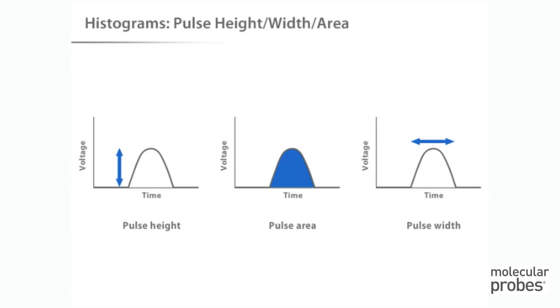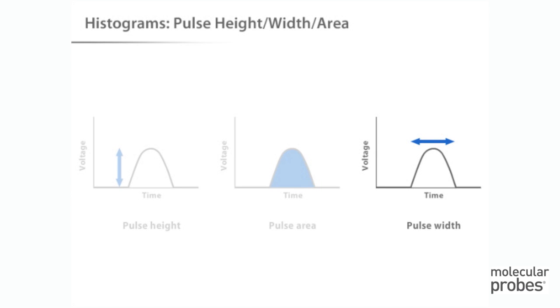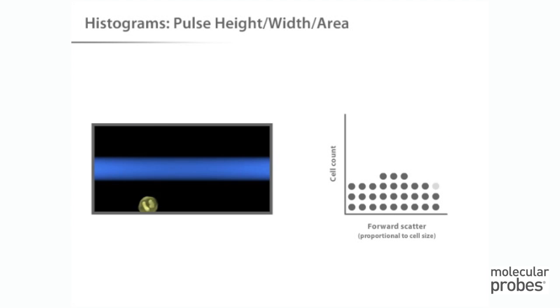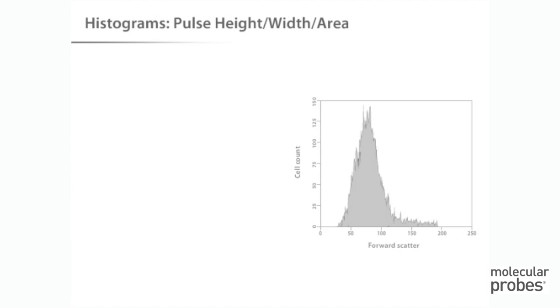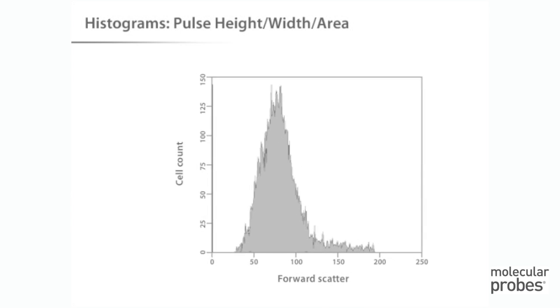Depending on the flow cytometer system, either pulse height or pulse area is used to quantify the size of the voltage pulse. Pulse width is used in certain special situations, such as DNA analysis, where it is important to distinguish single cells from double cell events. Once the pulse has been converted into a numerical value, that value can be used to plot the intensity of the event.